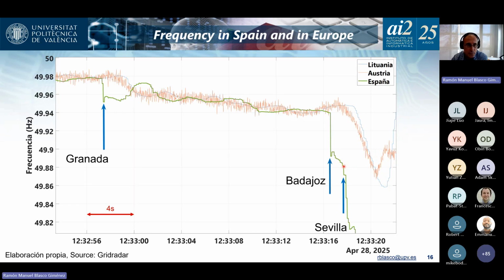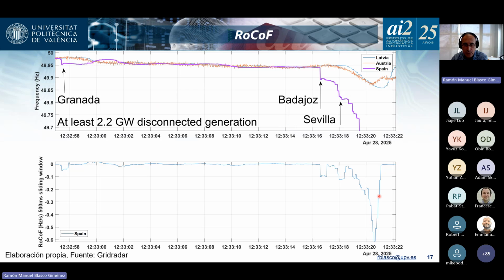The events have been captured with this open source frequency measurement. So you see that the first event was clearly captured, and the following events that were mentioned were also captured. So we did a small check of whether RoCoF was enough to cause the tripping, and as I said before, even though some generators tripped on RoCoF, it was not the main cause.